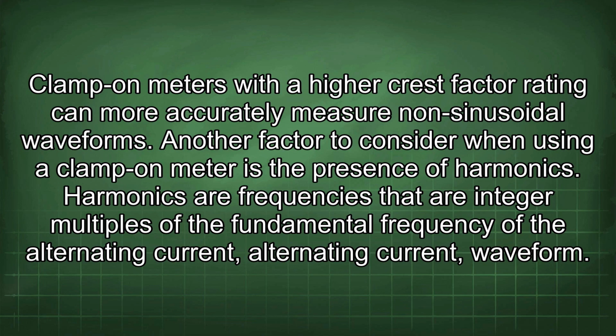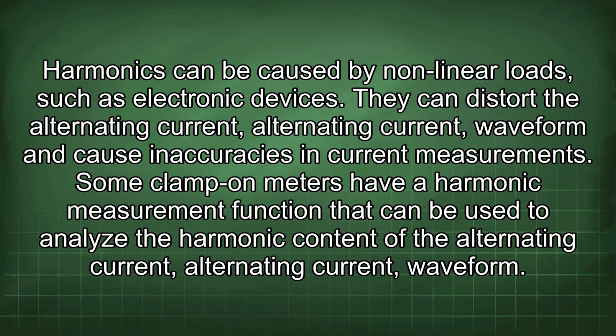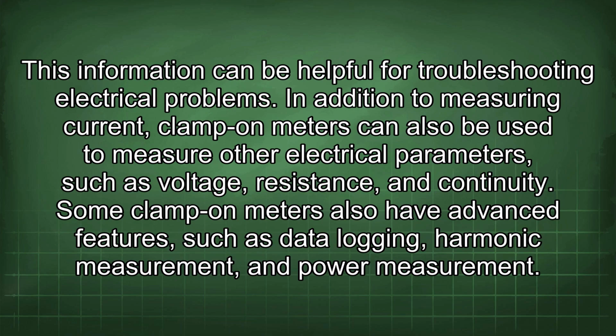Another factor to consider when using a clamp-on meter is the presence of harmonics. Harmonics are frequencies that are integer multiples of the fundamental frequency of the alternating current waveform. Harmonics can be caused by nonlinear loads, such as electronic devices. They can distort the alternating current waveform and cause inaccuracies in current measurements. Some clamp-on meters have a harmonic measurement function that can be used to analyze the harmonic content of the alternating current waveform. This information can be helpful for troubleshooting electrical problems.